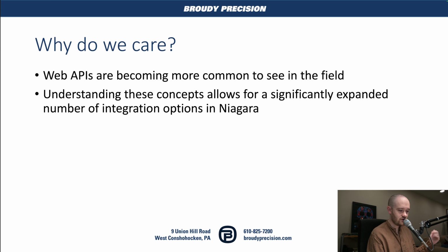These could be meters from startups or things like that, where you may not see the traditional BACnet IP or Modbus TCP options available, but instead there's a web API that you have to talk to at the company's servers somewhere else, not even locally in your building. So understanding these concepts allows you to make use of those APIs in a way that doesn't require you to build out a driver or something like that within Niagara, and it gives you the flexibility to pull in the information that you exactly need.